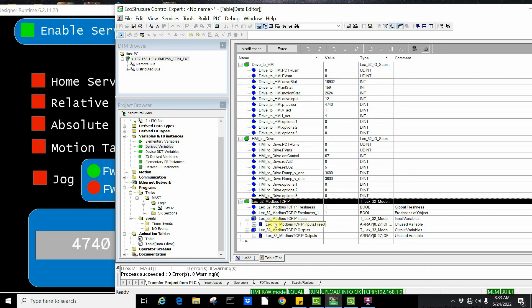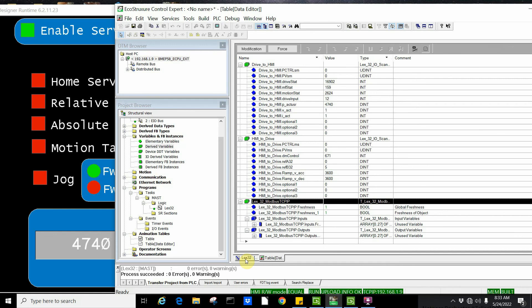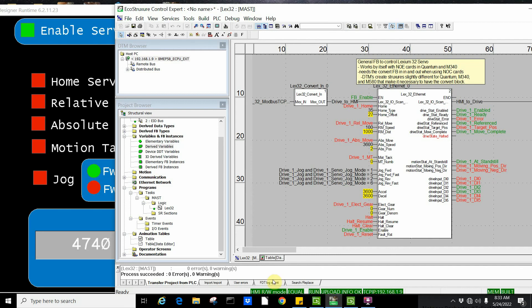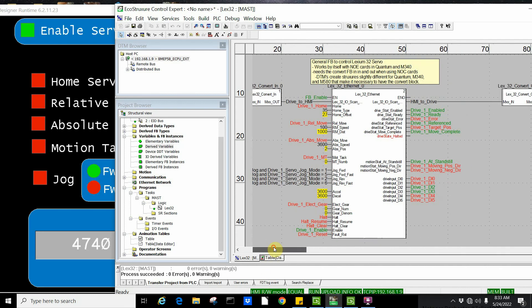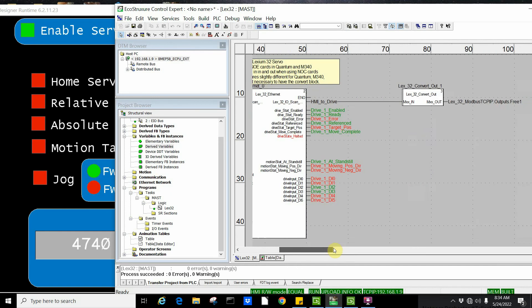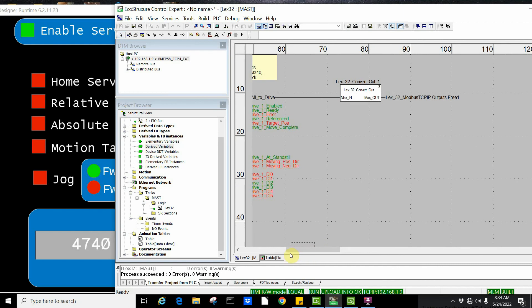All I need to do is in the inputs line, this part of the structure up with the input to my block, and the outputs I left as generic bytes as well. When I do a scan, here's my 0 to 27 part of the scan that I created going into the drive, and then it's getting all the information for the output. The control part of it takes the pins that we have here and uses the structured text and puts it out going out to commands to the drive. I simply line that up with the proper structure of the 0 to 27 for the bytes going into the scan and the application works.